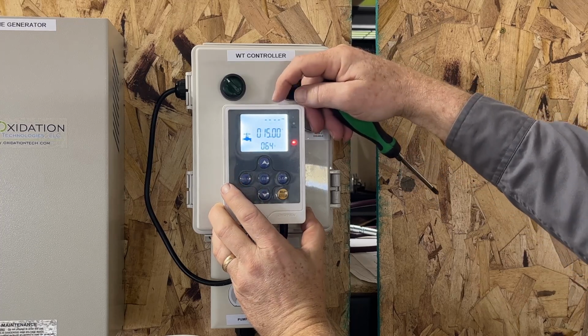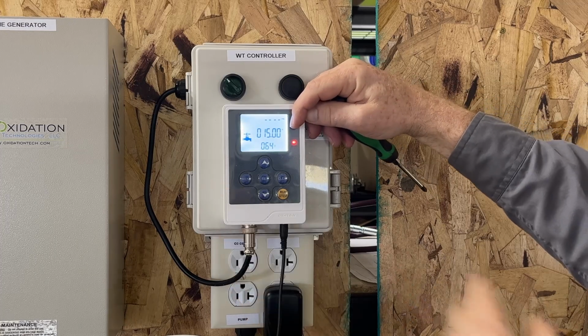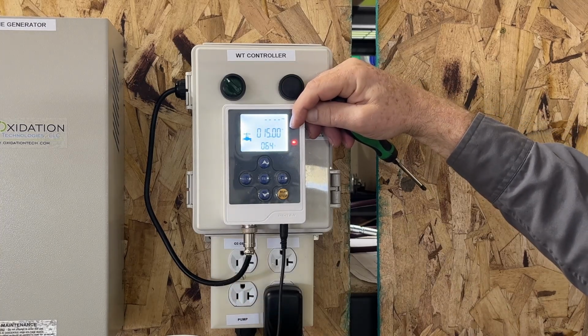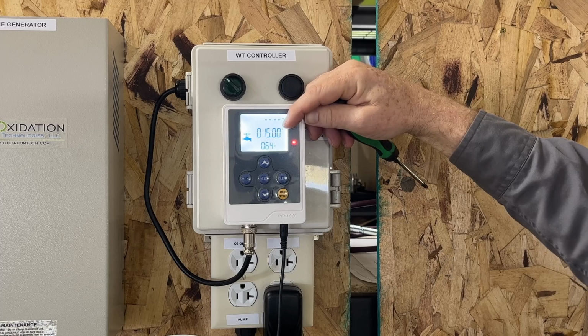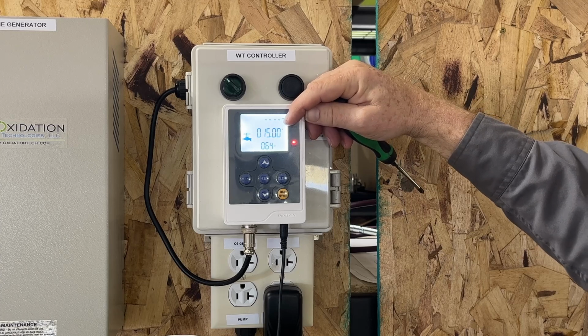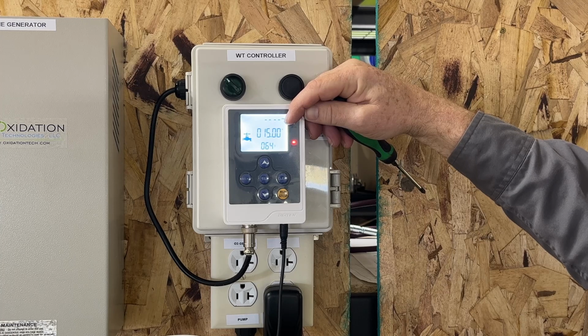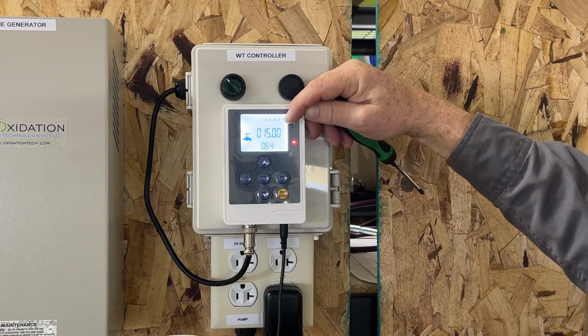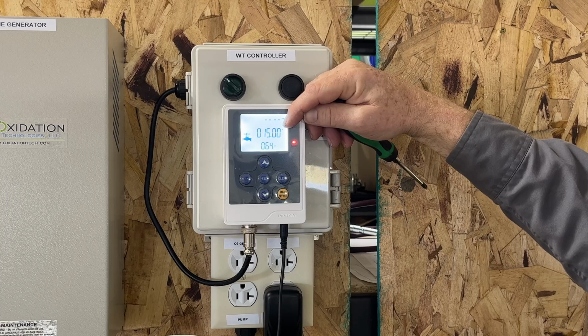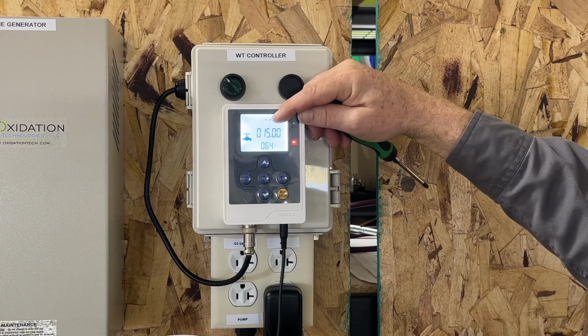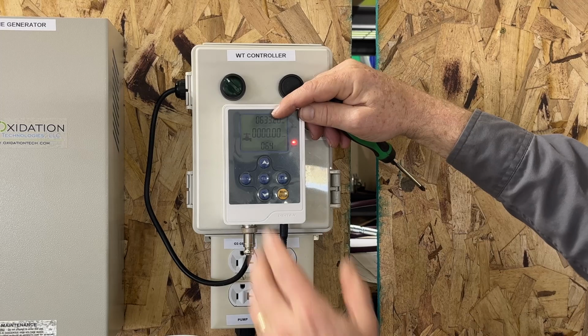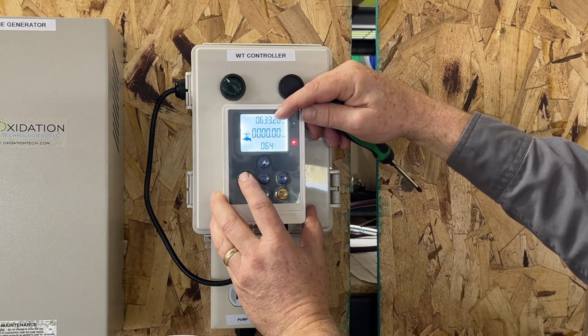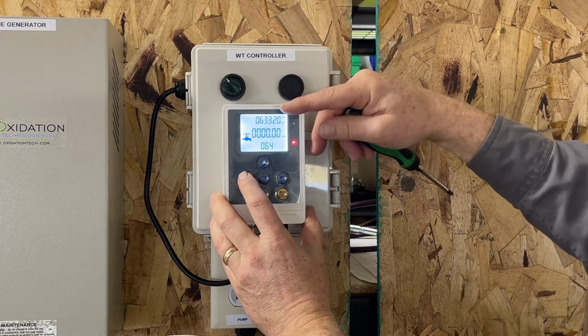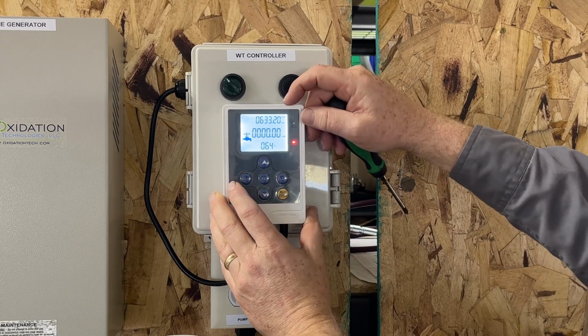When it gets to PW, that's changing the K value. The K value is used to calibrate this flow sensor. 15 is matched up pretty well with this particular flow sensor. It's a rough estimate of how many gallons a minute are being used. You could put a 5-gallon bucket and just test your output to make sure that it's right. But if you feel that it's reading high, you can change that number a little bit lower, a little bit higher. It'll change the K value. Those directions are in the manual.